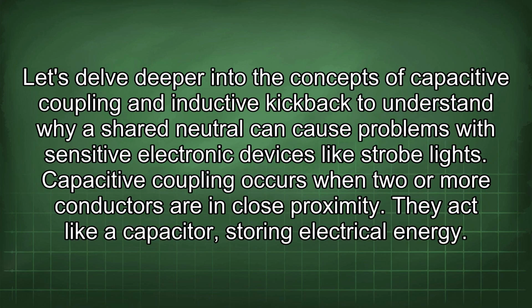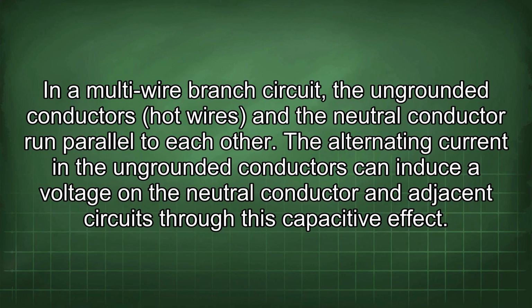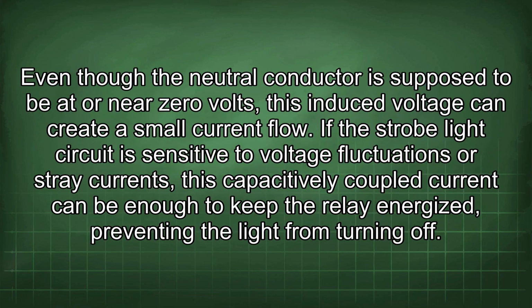Let's delve deeper into the concepts of capacitive coupling and inductive kickback to understand why a shared neutral can cause problems with sensitive electronic devices like strobe lights. Capacitive coupling occurs when two or more conductors are in close proximity. They act like a capacitor, storing electrical energy. In a multi-wire branch circuit, the ungrounded conductor's hot wires and the neutral conductor run parallel to each other. The alternating current in the ungrounded conductors can induce a voltage on the neutral conductor and adjacent circuits through this capacitive effect. Even though the neutral conductor is supposed to be at or near 0 volts, this induced voltage can create a small current flow.